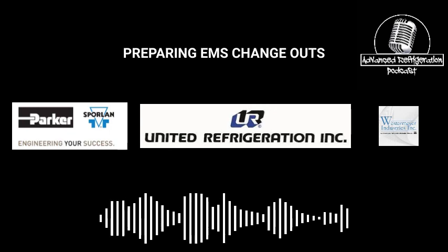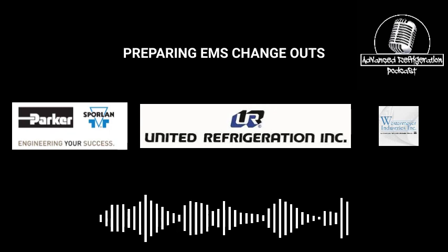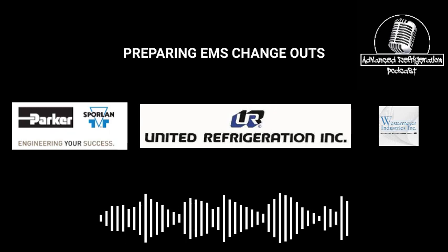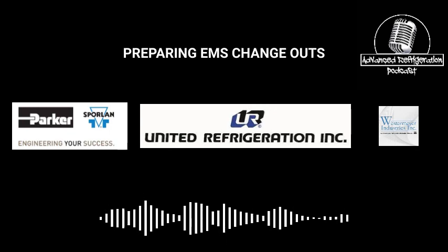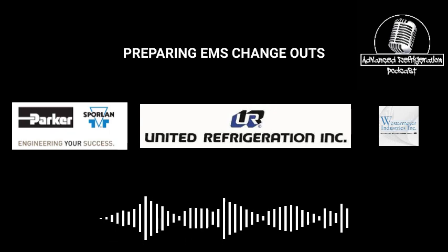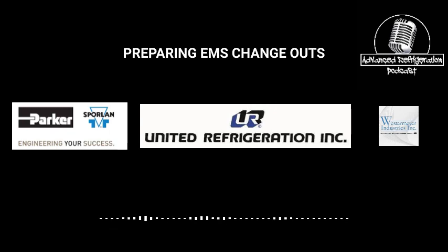If you're doing stores and you're converting multiple controllers into one controller, that's a whole other thing. You need to plan out your comm loop, because you don't want to start with the first controller and be like, oh, now I've got a star here, when you could have just run two comm lines out and spliced it in the middle of the network. That's one thing you guys need to really pay attention to. Are you going from 4 controllers to 1 Emerson controller? Well, now you've got to lay out your comm lines. You may have to pull some wire before you start in order to not end up with stars.